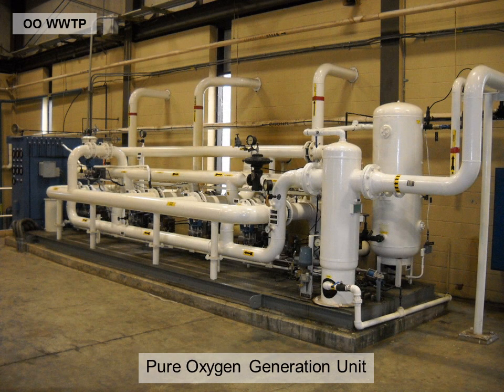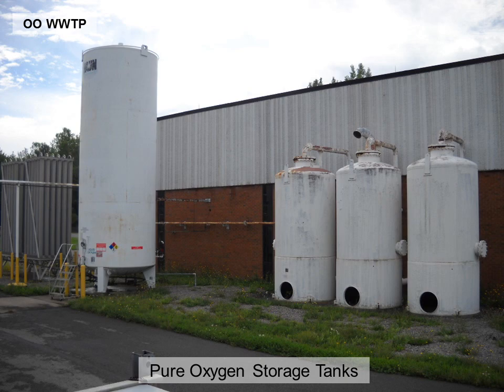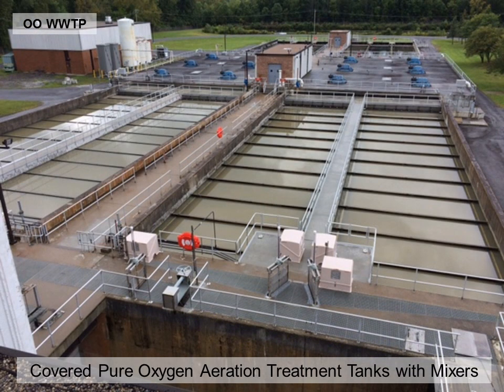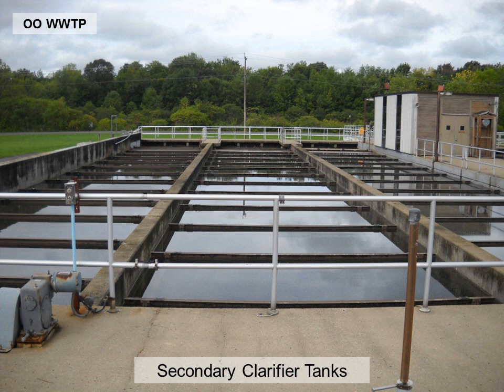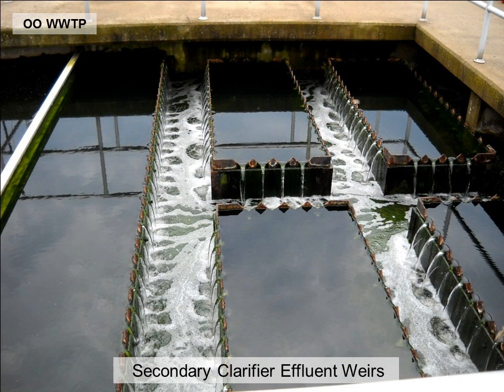Pure oxygen is generated on site and is used in the activated sludge process. Pure oxygen is also stored on site. The wastewater then flows into covered aeration tanks where it is mixed with pure oxygen, which facilitates biological nutrient removal. The mixed liquor from these tanks then flows into secondary clarifiers where settling occurs. Solids are collected in these tanks and effluent flows over the weirs.